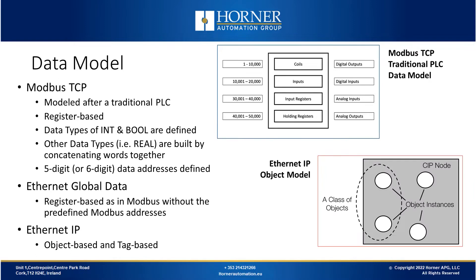Let's begin comparing these protocols, starting with the data model. Modbus TCP was based on Modbus, invented in the late 1970s. At that time, it made sense to model the protocol on a traditional PLC, which were register-based and strictly consisted of integer and boolean data types. Over time, other data types like floating point and double integer became popular. Companies like Horner adapted Modbus to support additional data types by concatenating word-type registers together to create floating point, double integer, and other data types.